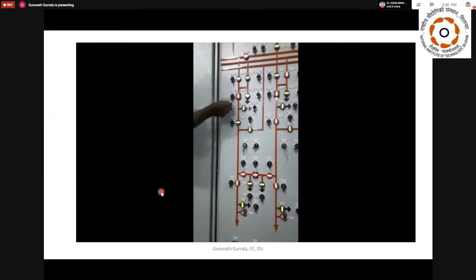See, now these two are on, so it will not operate. Now both circuit breakers are off, so now this can be operated. That is, this line isolator is interlocked with this circuit breaker and this circuit breaker.